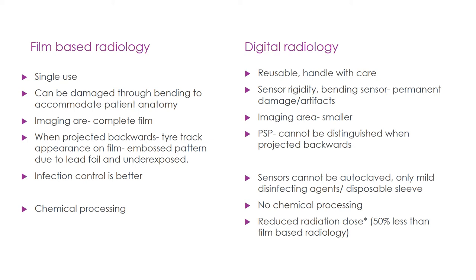Infection control is considered better with film-based radiology because you use one film and dispose of the packet, but infection control with sensors is also good now. Sensors cannot be autoclaved, but mild disinfectant agents can be used; the best option is to use a disposable sleeve covering the entire sensor to protect it from saliva and maintain hygiene. Lastly, there is no chemical processing in digital radiology — it's totally eliminated — making it more environment friendly, and there is a 50% reduced radiation dose compared to film-based radiography.